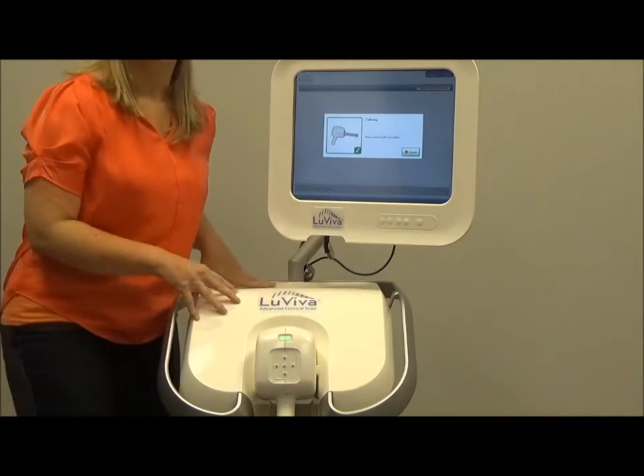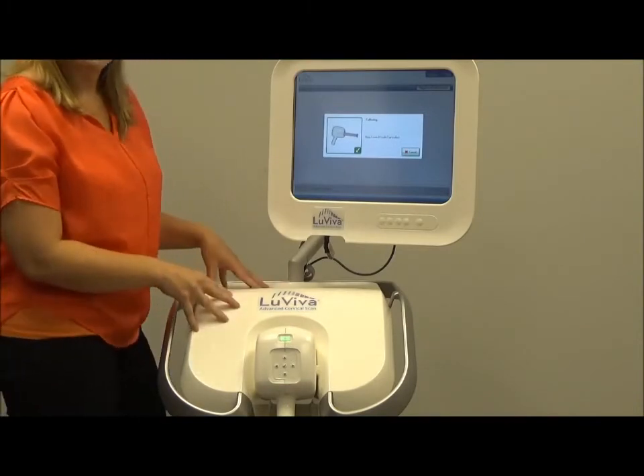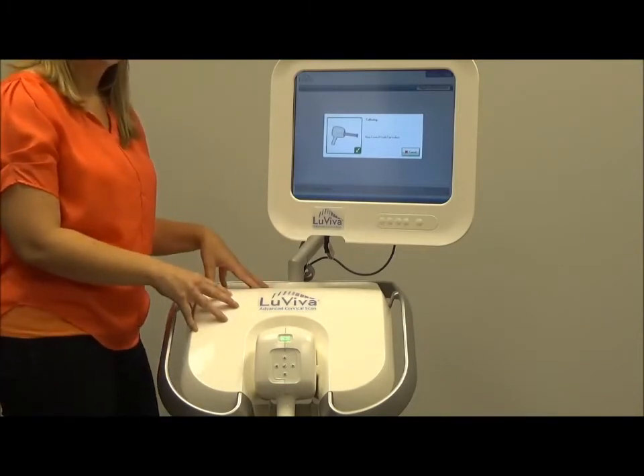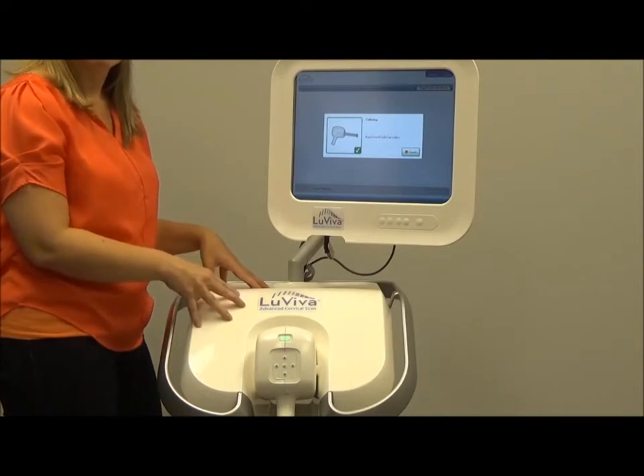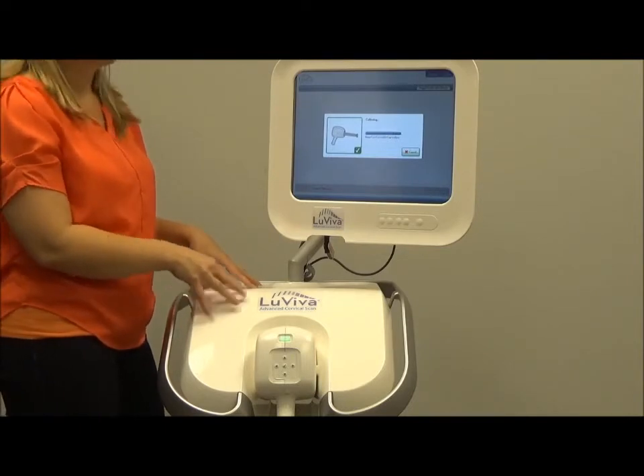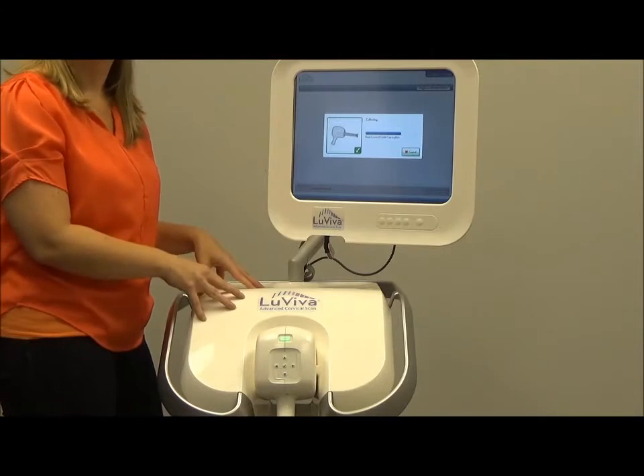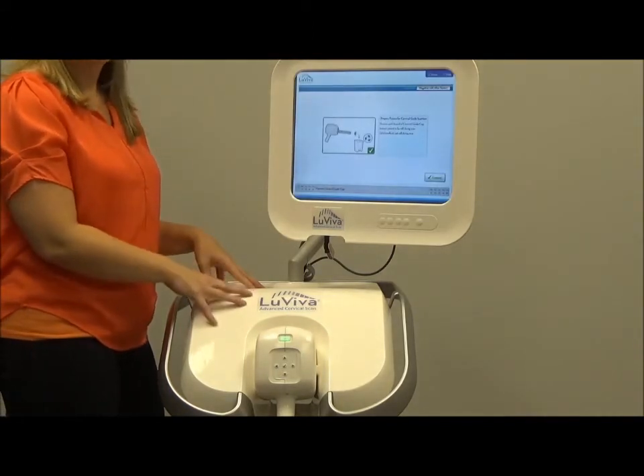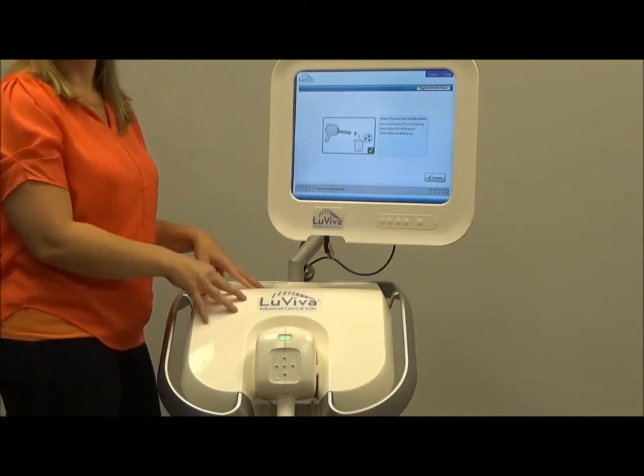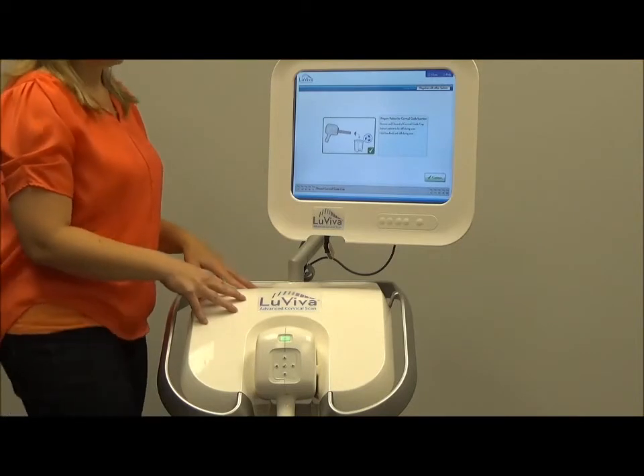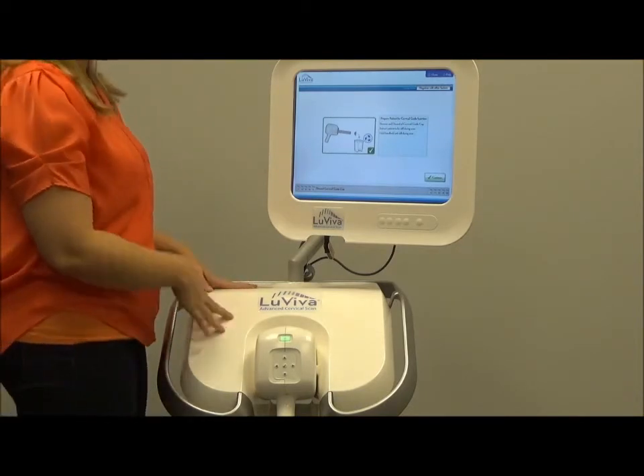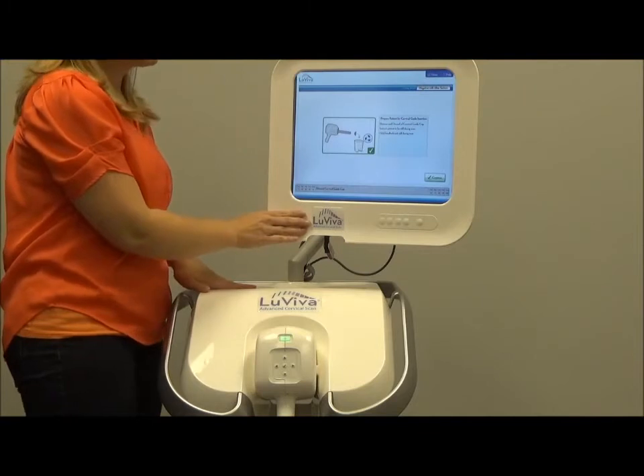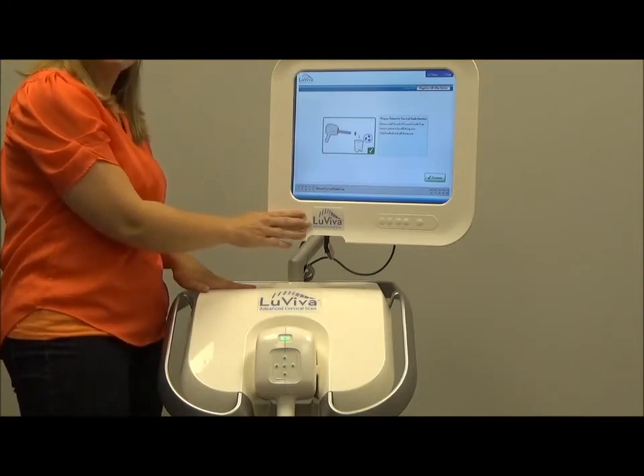During calibration, the device is doing its own testing. It's testing the computer, the lamp, and all the other components within the device to make sure that everything is working properly before the actual scan. If there's any problems found within this time, you would be notified. Once calibration is complete, you're now at step 5. This is when the patient can be prepared for the examination.